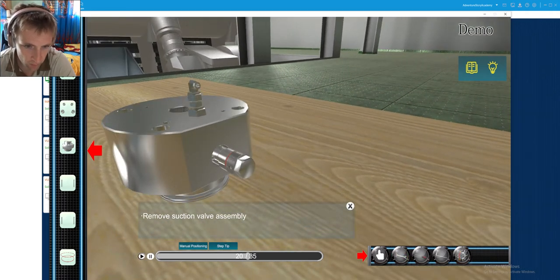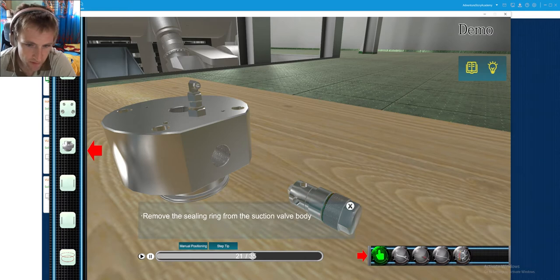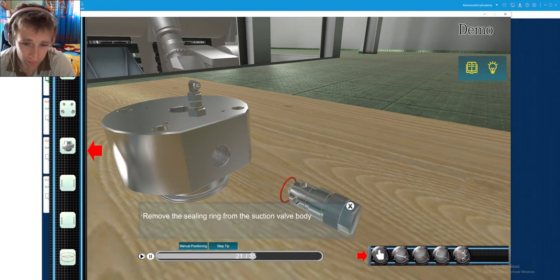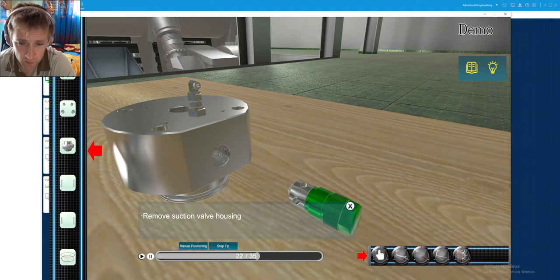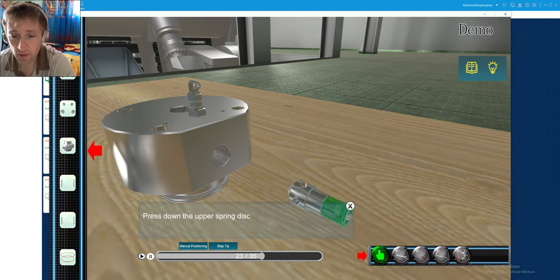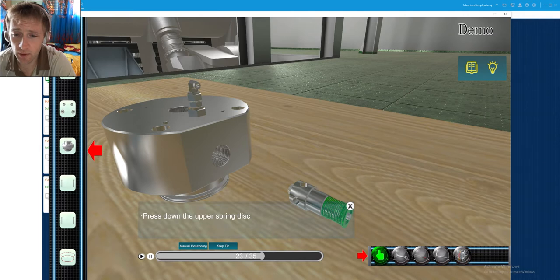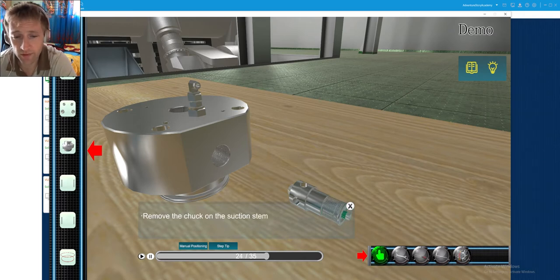Here we will remove also the suction valve. This kind of valve is really really important to be inspected and to be in good condition. You can see also the sealing surfaces, and as I have seen we had only one suction valve on board the vessel.